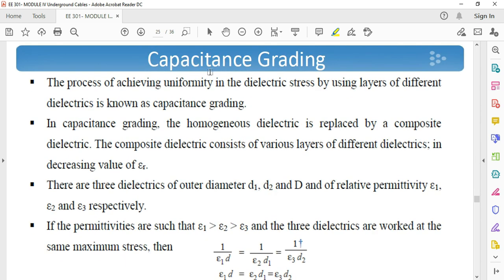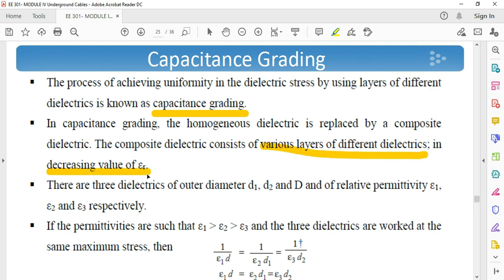First is capacitance grading. The process of achieving uniformity in the dielectric stress by using layers of different dielectrics is known as capacitance grading. Here, a number of layers of dielectrics with different values of permittivity are used. In capacitance grading, the homogeneous dielectric is replaced by a composite dielectric. The composite dielectric consists of various layers in decreasing value of permittivity. There are three dielectrics of diameter D1, D2, and capital D, with relative permittivity E1, E2, and E3 respectively, as shown in the figure.